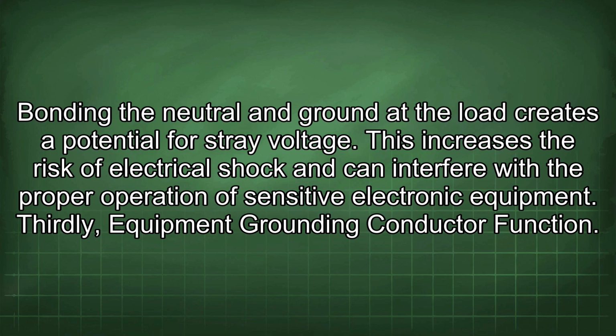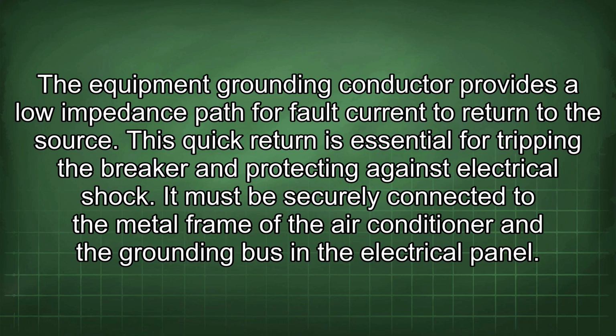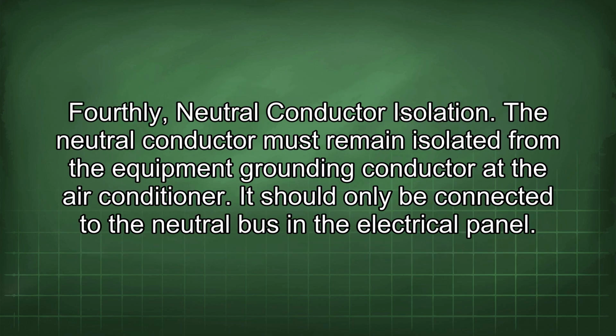Thirdly, equipment grounding conductor function. The equipment grounding conductor provides a low impedance path for fault current to return to the source. This quick return is essential for tripping the breaker and protecting against electrical shock. It must be securely connected to the metal frame of the air conditioner and the grounding bus in the electrical panel. Fourthly, neutral conductor isolation. The neutral conductor must remain isolated from the equipment grounding conductor at the air conditioner. It should only be connected to the neutral bus in the electrical panel.